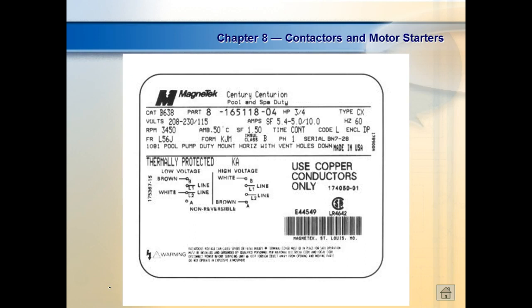But when we come over here and look at our current, 5.4 amps, why does it require more current at 208 volts than it does on 230? So on 208, it's going to require 5.4. On 230, it's going to require 5. I thought Ohm's law says that when voltage goes down, current goes down. So why does the lower voltage require more current?